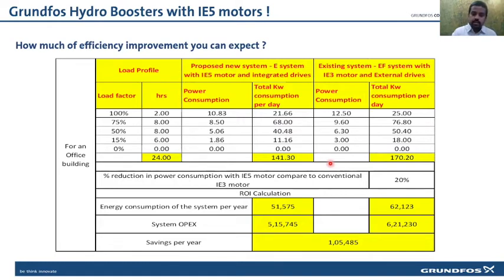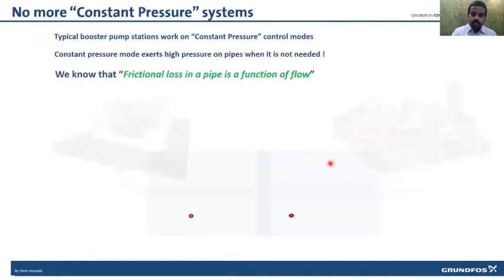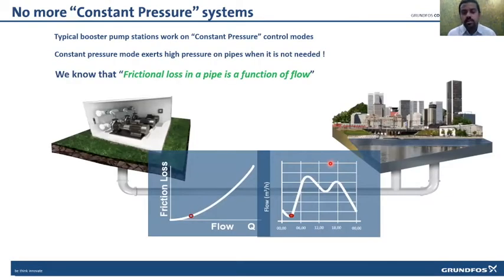And the second area is on the operational philosophy. When we talk about a hydro booster system, it is not a pump, it's a system. So we need to understand how we control it as a system to have better energy saving. Till today, the control mode we use to make the hydro boosters work is a constant pressure control mode. So let me put more details into it for a better understanding. When we say constant pressure, when we design a head for a hydro booster pump, we take three parameters. One is the static height of a building, the second is the terminal pressure, and the third is the frictional loss.